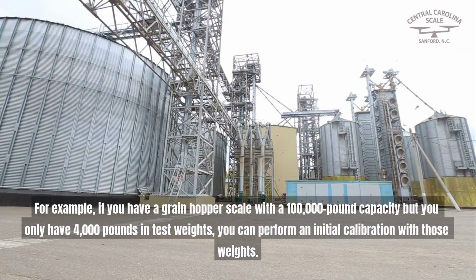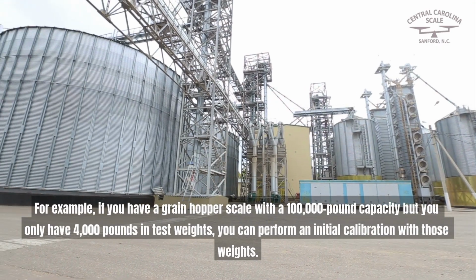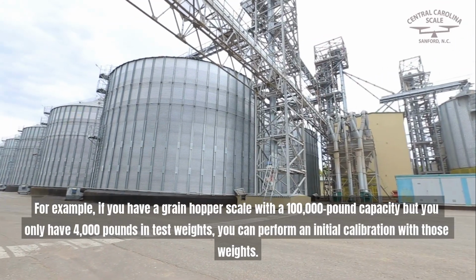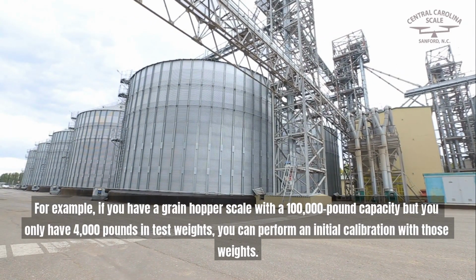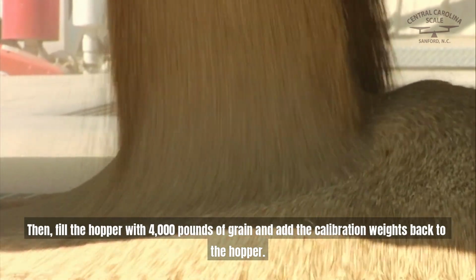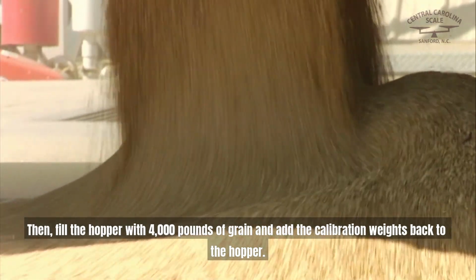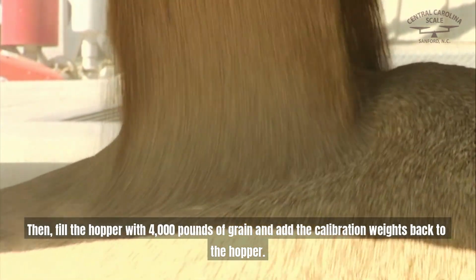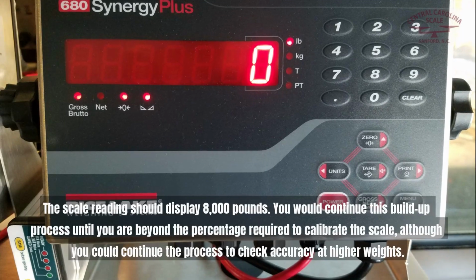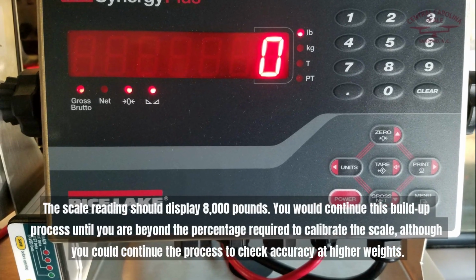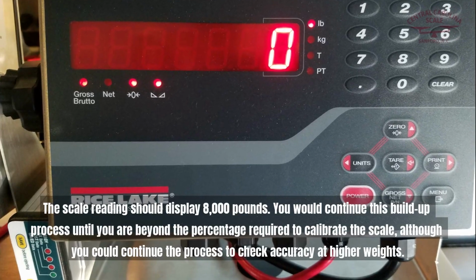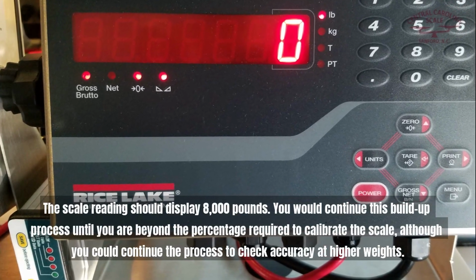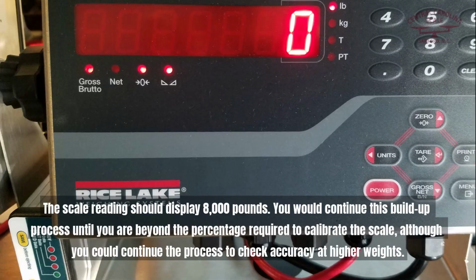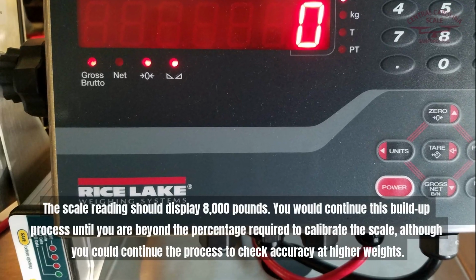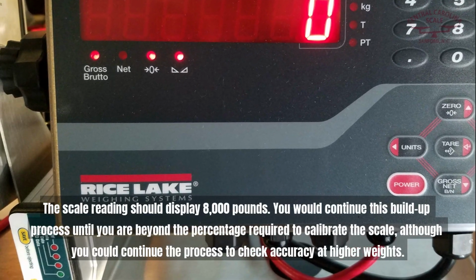For example, if you have a grain hopper scale with a 100,000 pound capacity, but you only have 4,000 pounds in test weights, you can perform an initial calibration with those weights. Then fill the hopper with 4,000 pounds of grain and add the calibration weights back to the hopper. The scale reading should display 8,000 pounds. You would continue this build-up process until you are beyond the percentage required to calibrate the scale, although you could continue the process to check accuracy at higher weights.